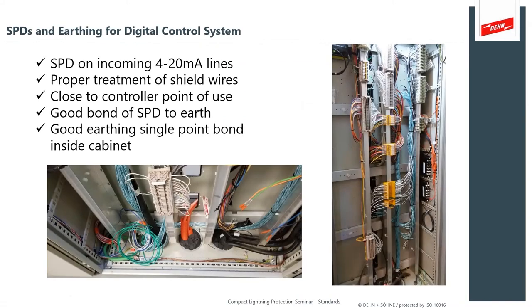SPDs on digital control systems. These are extensive systems that have transmitters and instrumentation scattered around a large plant. And here we have SPDs on the incoming 4 to 20 milliamp lines. Check the box. Proper treatment of the shield wires. Is that ground lifted? Is it installed on the other end? Close to the controller point of use.